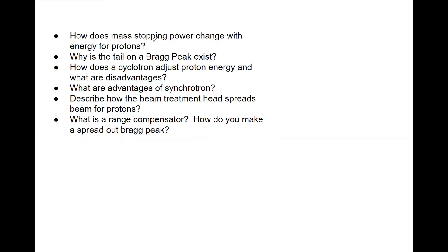First and foremost, the mass stopping power, or S over rho, is larger for low Z materials, so these slow protons down more than high Z materials. High Z also scatters more, and you pretty much have to use both high Z and low Z materials to control scattering but also lower beam energy.